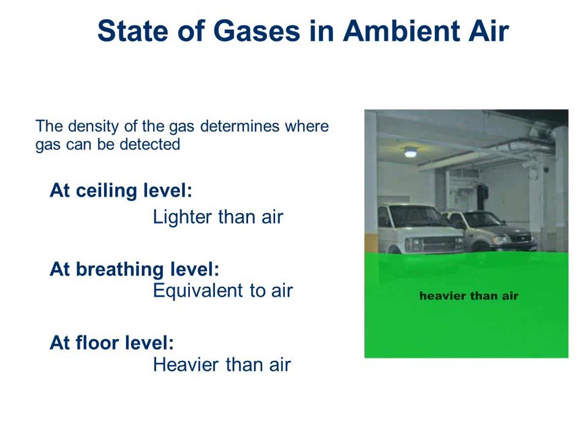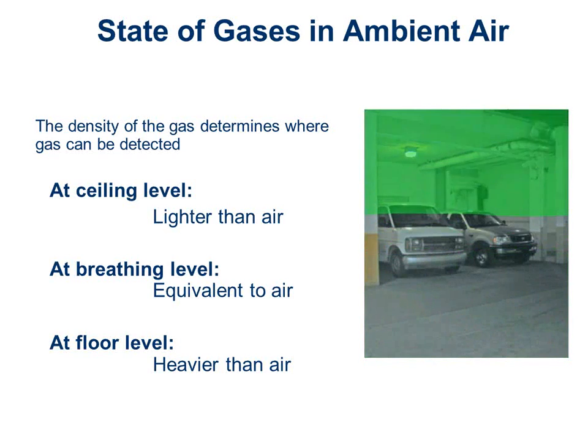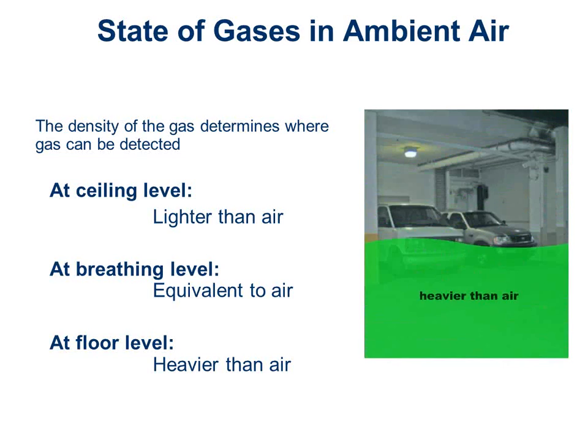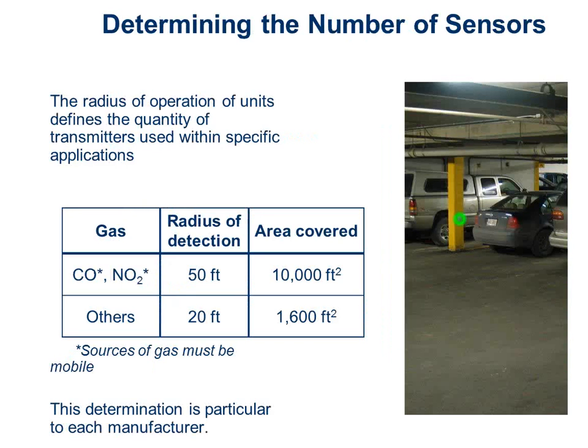So you'll see some of the specs I'm going to show you here. It'll say measure 1 foot off the floor or 1 foot below the ceiling, right? Or measure it at the breathing zone level, because it just depends on whether the gas is heavier or lighter than air. And I want to detect it in the first place that I can likely find it, so I can do something about it sooner rather than later.